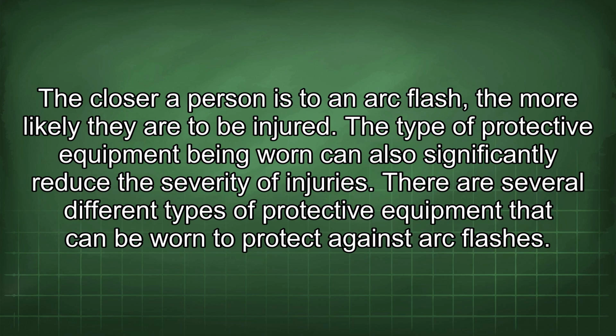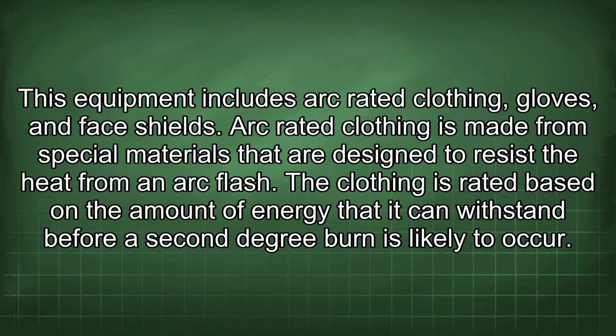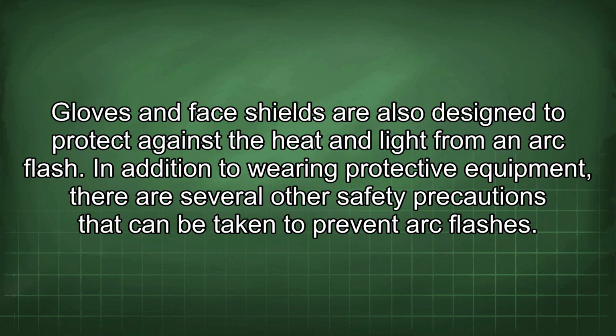There are several different types of protective equipment that can be worn to protect against arc flashes. This equipment includes arc-rated clothing, gloves, and face shields. Arc-rated clothing is made from special materials that are designed to resist the heat from an arc flash. The clothing is rated based on the amount of energy that it can withstand before a second-degree burn is likely to occur. Gloves and face shields are also designed to protect against the heat and light from an arc flash.